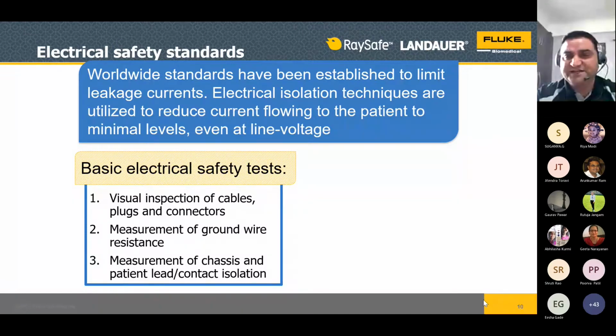The basic electrical safety test is visual inspection of cables. You can check whether there is any wear and tear or not. You cannot use those kinds of cables. Measurement of ground wire resistance we can do. Measurement of chassis and patient lead contact isolation. Have you ever seen, if you go to any place and touch any instrument, it gives an immediate shock to you? If somebody has experienced it, that also should not happen. So we have to ensure that the equipment is verified for all those things.